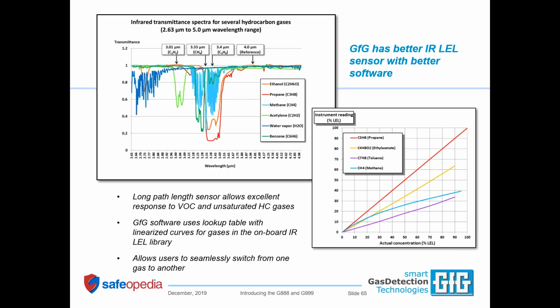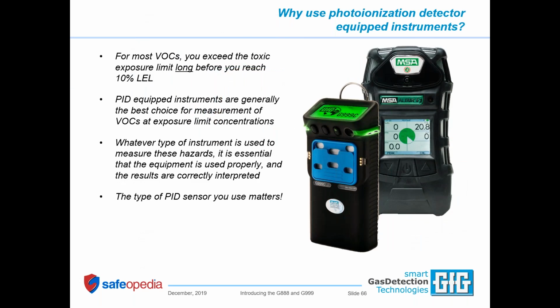If you want to calibrate the instrument for propane, you set it up on the propane curve. You pick it from the library, and then your readings are accurate. These capabilities allow you to seamlessly move from one gas to another in the instrument's onboard library. So unlike the instrument in the last slide, in the case of the G888 and the G999, you really have the ability to measure more than just plain old garden pure methane.